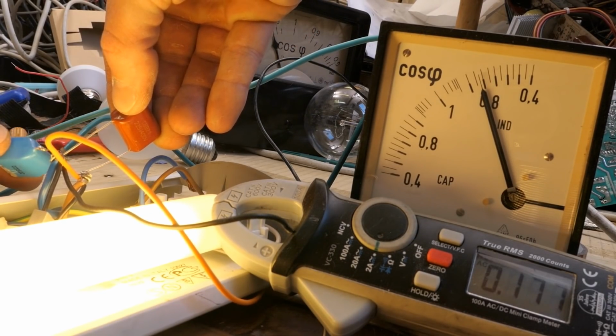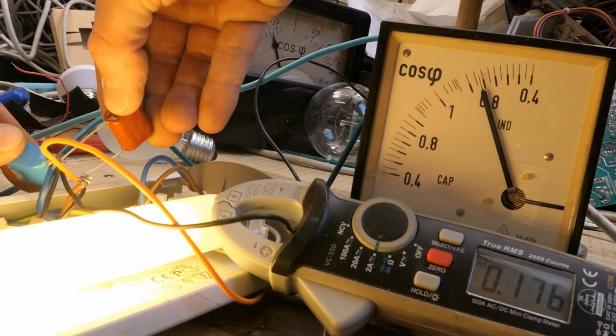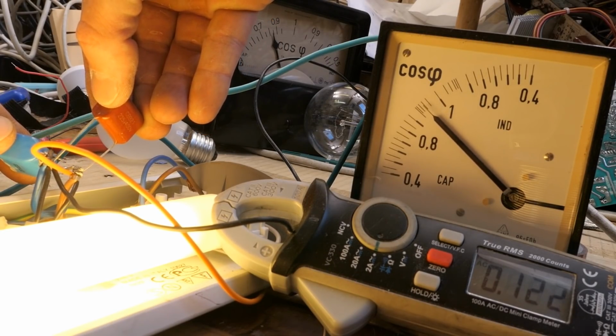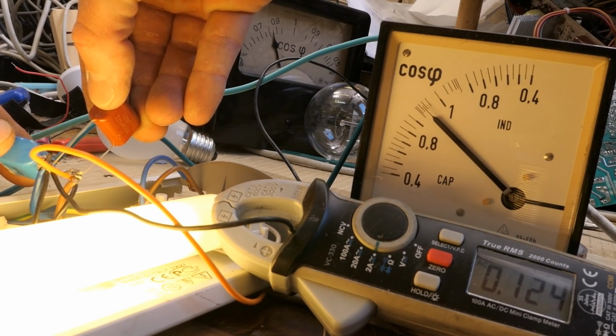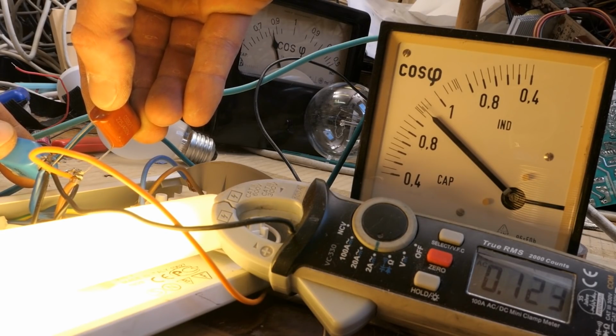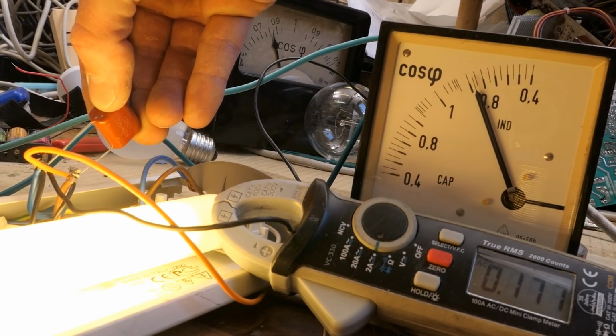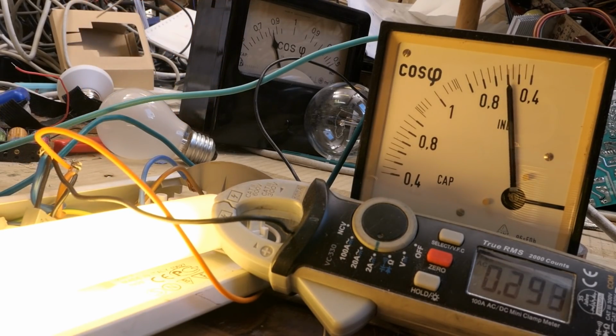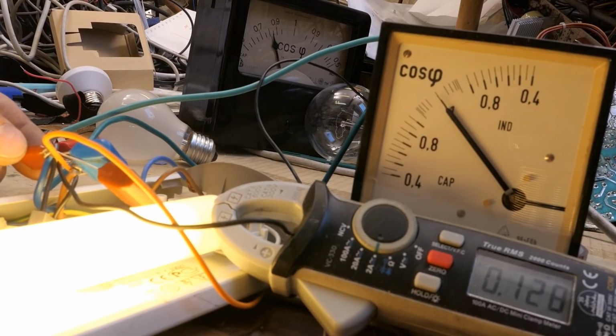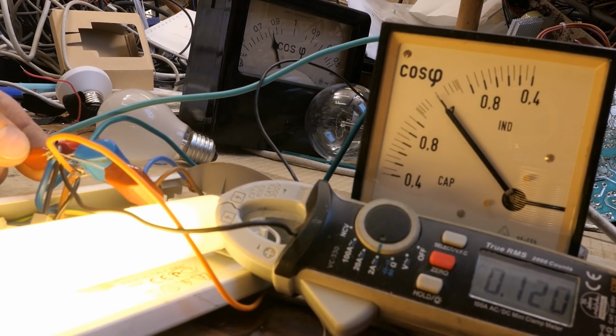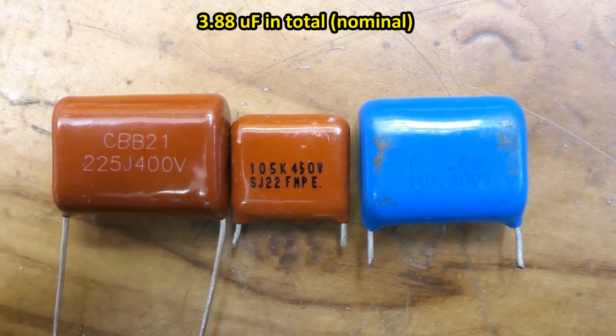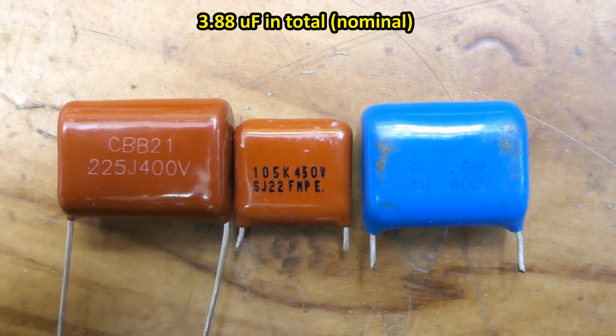Oh, 2.2 micro, and one more. And now it's slightly overcompensated, and it goes a bit into capacitive. This is 4.4 micro, 2.2 micro, no compensation. Now I found a combination of capacitors which brings it to a unity power factor. 2.2 micro plus 1 micro plus 0.68 micro.